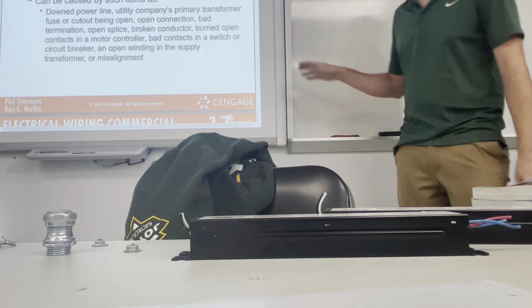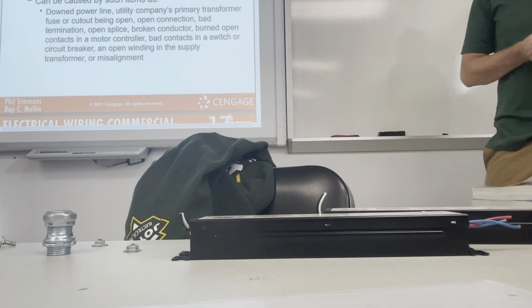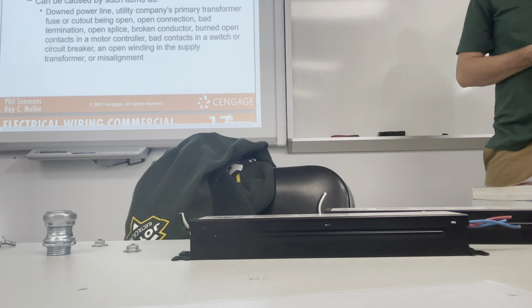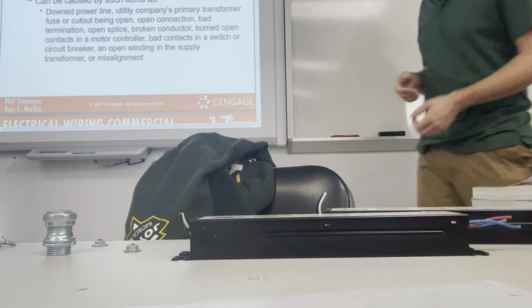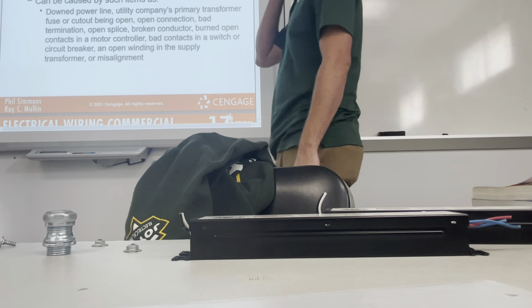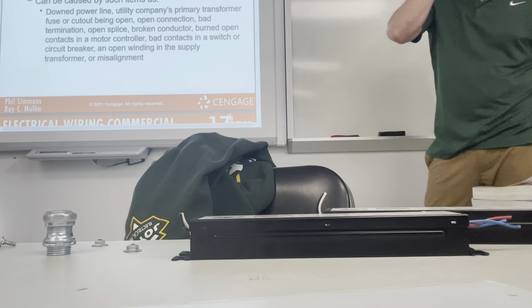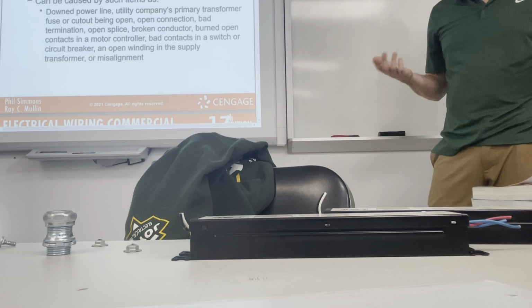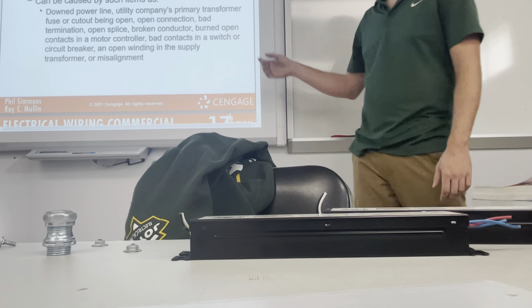Crazy, huh? So just make sure, all this can cause it, but even the utility company could cause trouble. So just know what your phases are. It further helps to keep them color coded so you know if there's issues. But single phasing can be caused by pretty much anything. Normally it's just wear and tear in the lines. We said before in grounding and bonding that anything that's in conduit is open to damage, right? Well, it's all these issues.